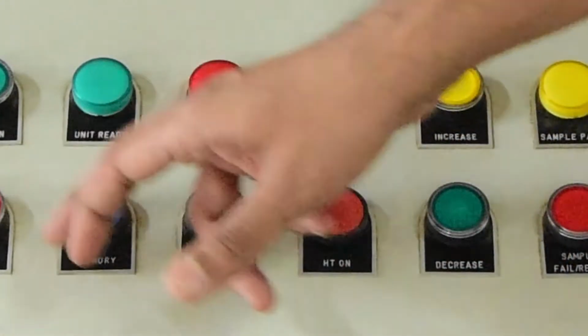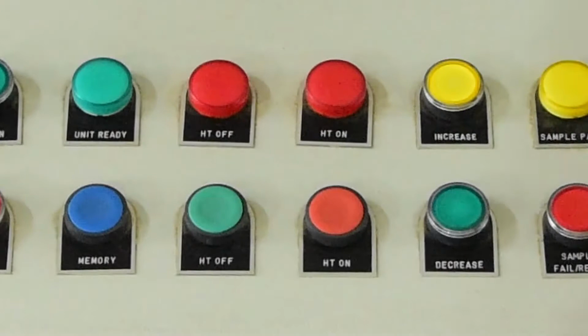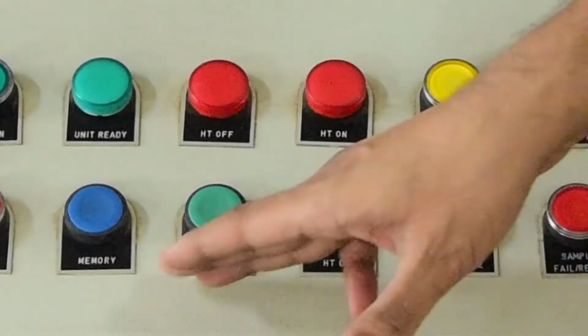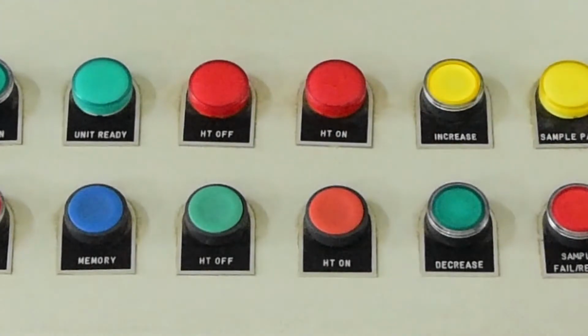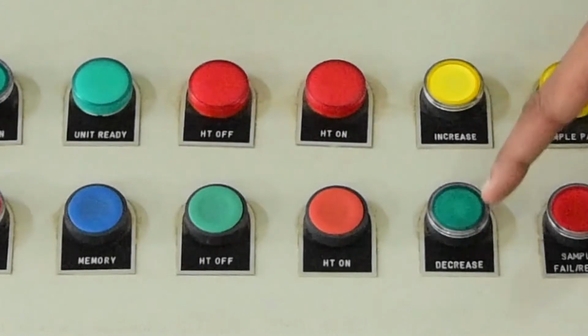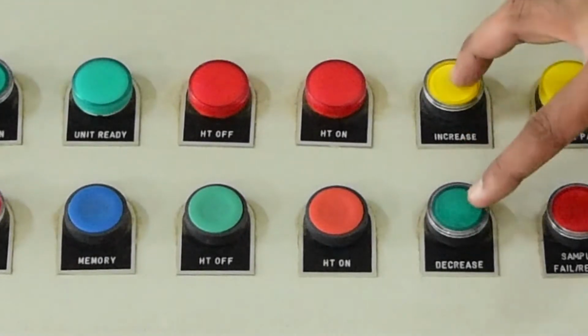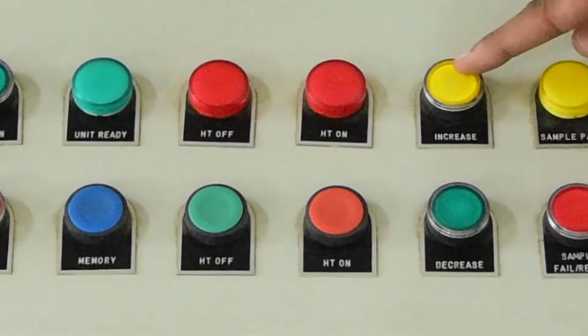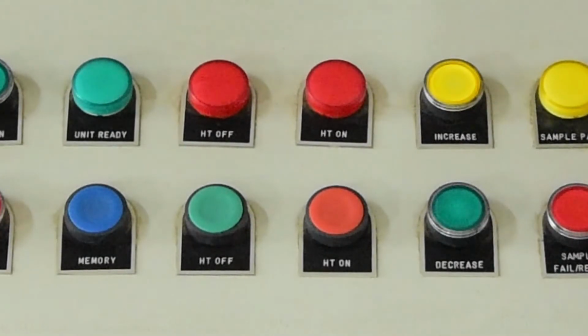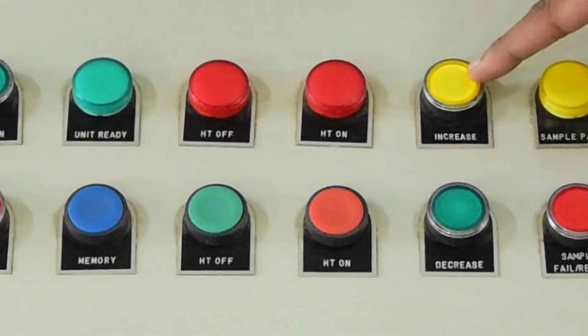Apart from HT on, HT off, and mains on, mains off, here this is a memory switch. If the sample fails, like we have seen in the solid insulator test, the memory switch will be able to memorize the observation based on the position of the variac that was used for setting the voltage. So HT on, HT off switches and their indicators are visible here. Now next, an important control is this green and yellow. These both are switches. The upper switch is to increase the voltage applied to the transformer output.